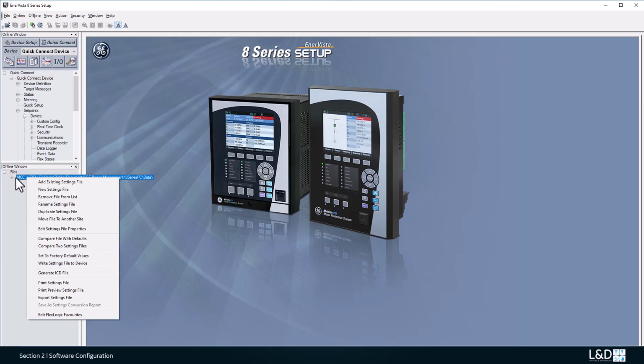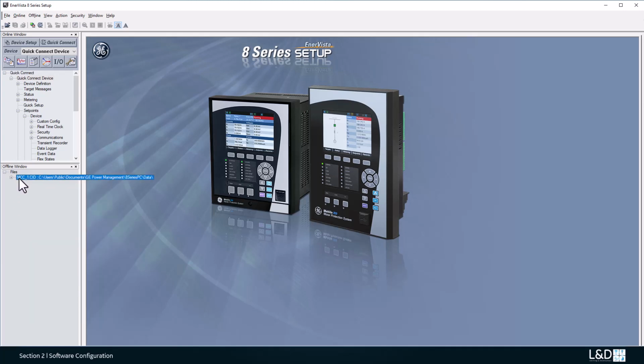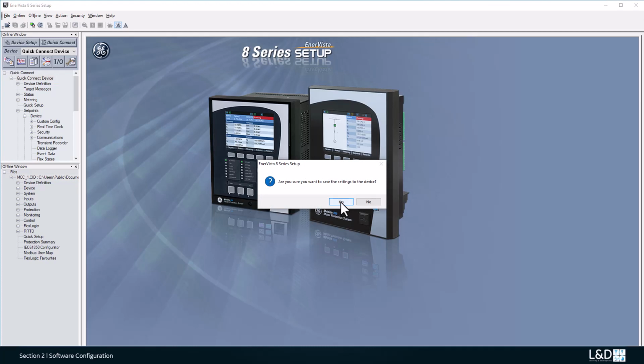There's another way. This is only available for the 8 Series platform, drag and drop. So you can make some changes in the offline setting file and drag this setting file and drop it over the device. Here is the quick connect device. Then we can just click yes. Then the setting file will be written back into the relay. Okay, we got a message: setting file successfully written to the relay.